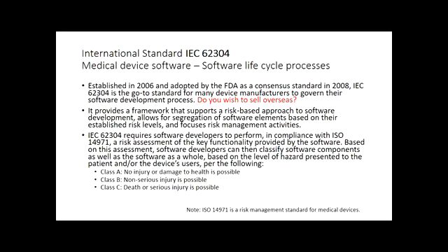So let's have a quick look at that standard. It's been around for a while. When software exploded, probably around the early 2000s, this standard came out and it was adopted by pretty much everyone. Now Australia does not require that you use it. However, a lot of other countries do. So if you want to sell your medical device overseas, you would need to be compliant with the standard. It's one of those optional things, but it's a really good way to illustrate that you meet the relevant essential principle.